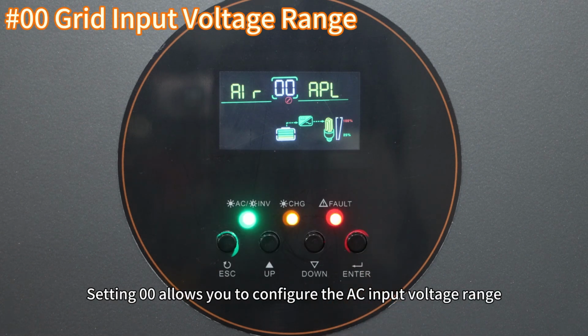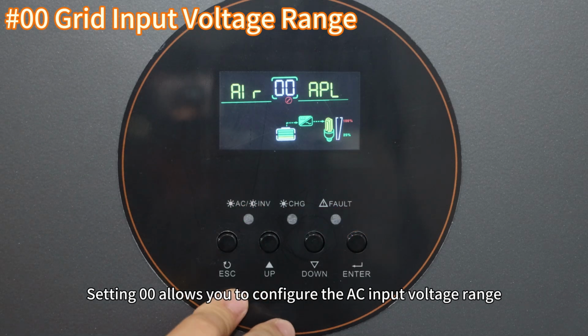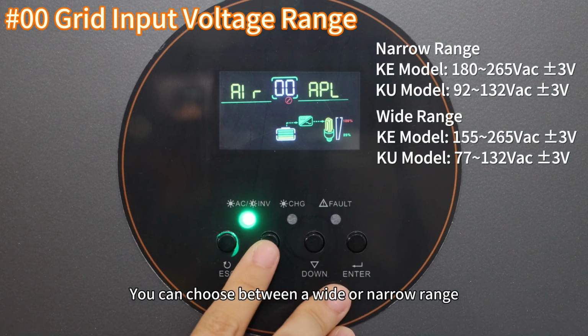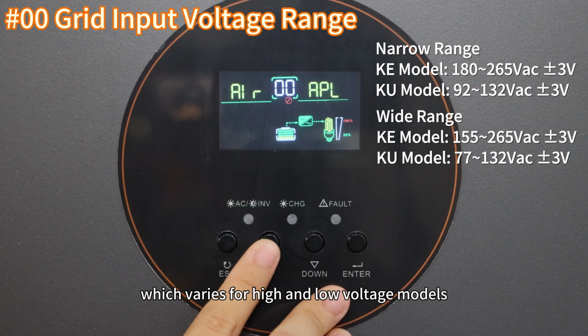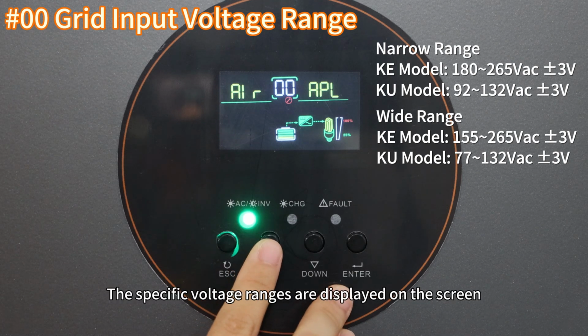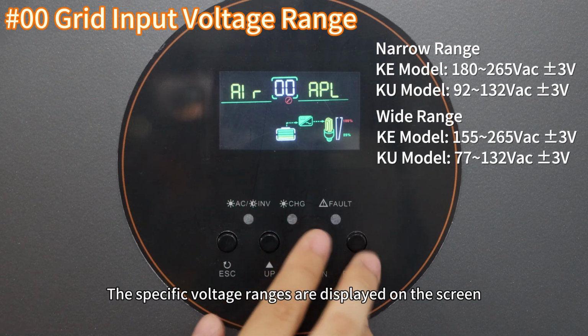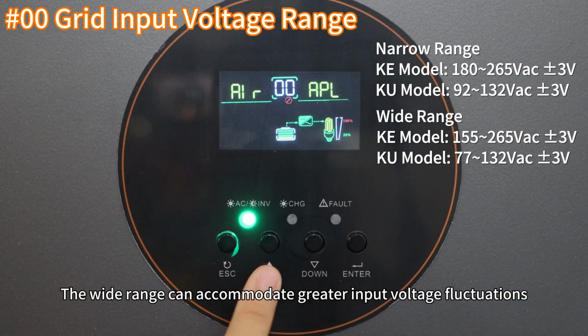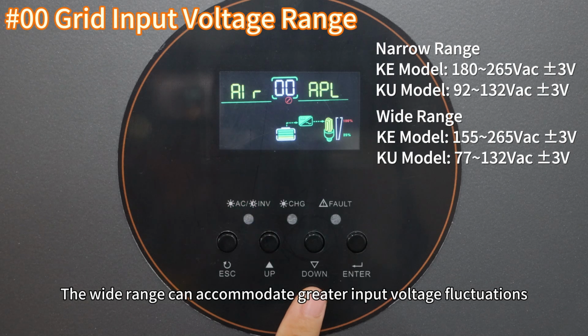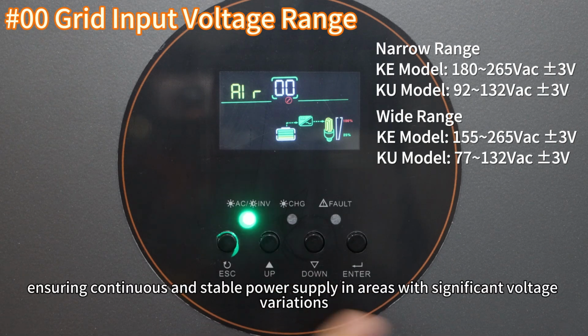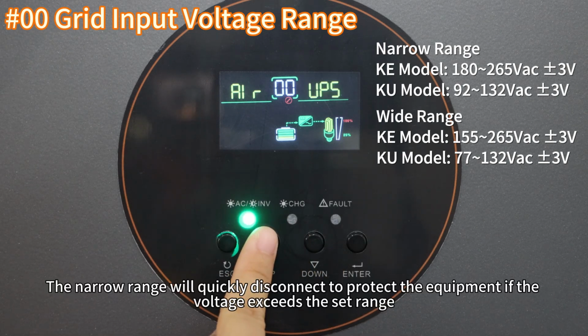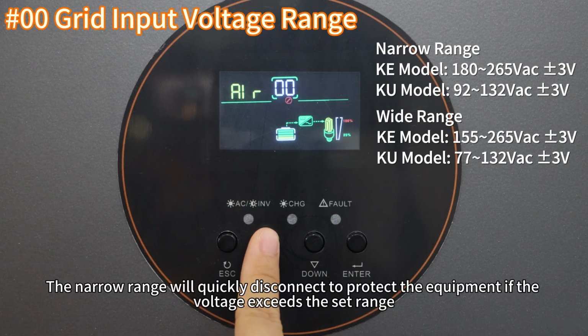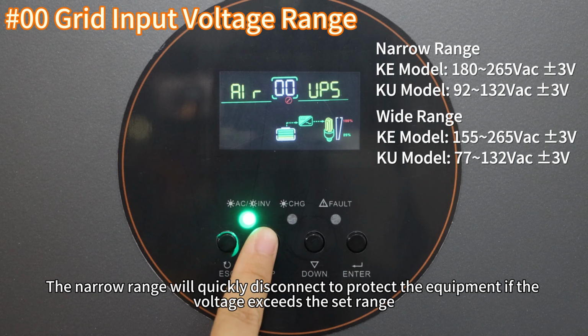Setting 0 allows you to configure the AC input voltage range. You can choose between a wide or narrow range, which varies for high and low voltage models. The specific voltage ranges are displayed on the screen. The wide range can accommodate great input voltage fluctuation, ensuring continuous and stable power supply in areas with significant voltage variations.